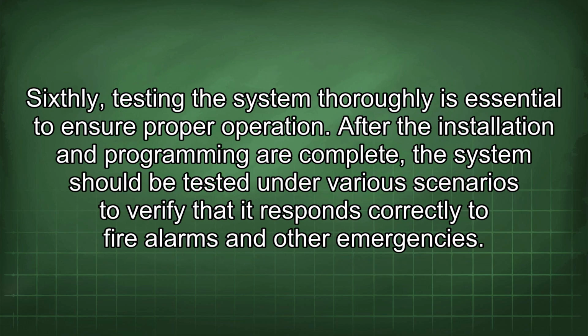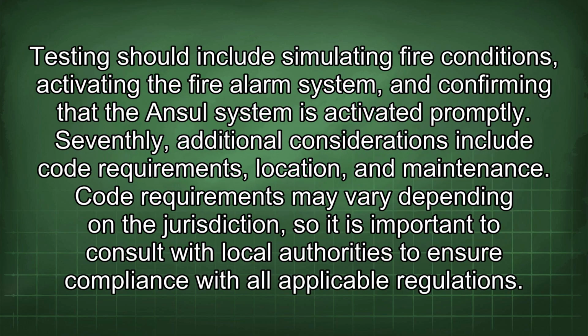Sixthly, testing the system thoroughly is essential to ensure proper operation. After the installation and programming are complete, the system should be tested under various scenarios to verify that it responds correctly to fire alarms and other emergencies. Testing should include simulating fire conditions, activating the fire alarm system, and confirming that the Ansul system is activated promptly.